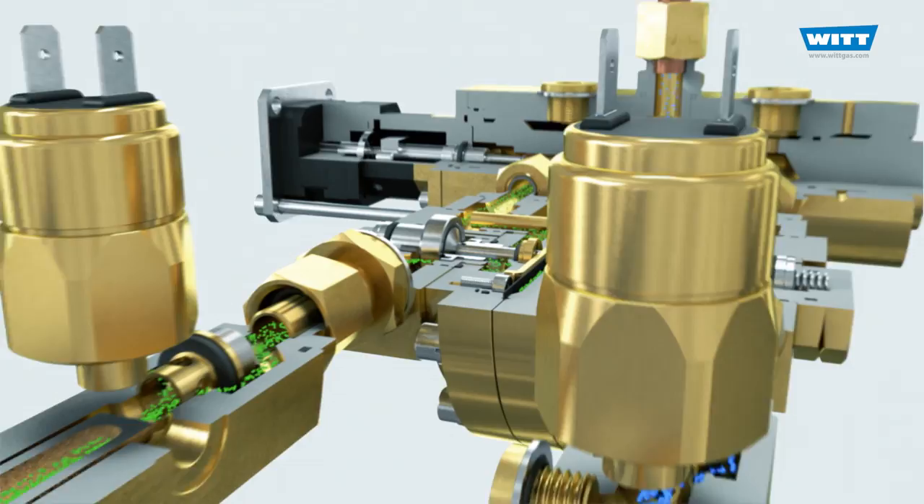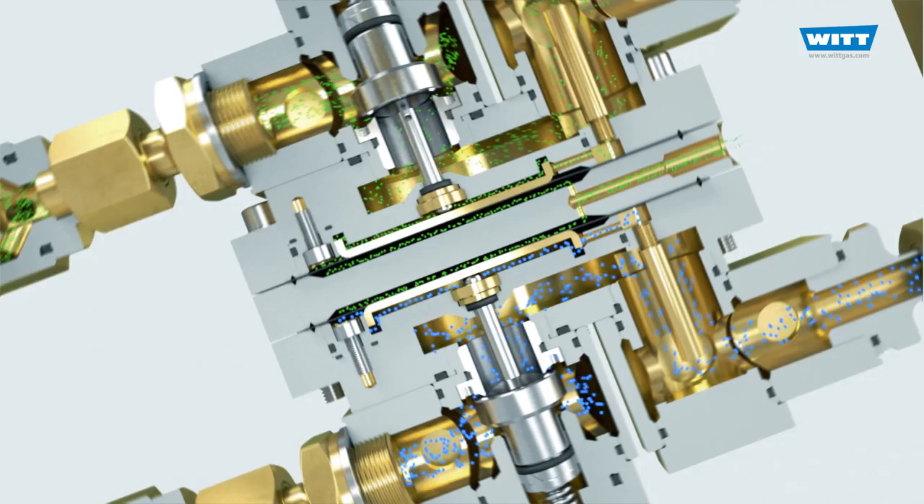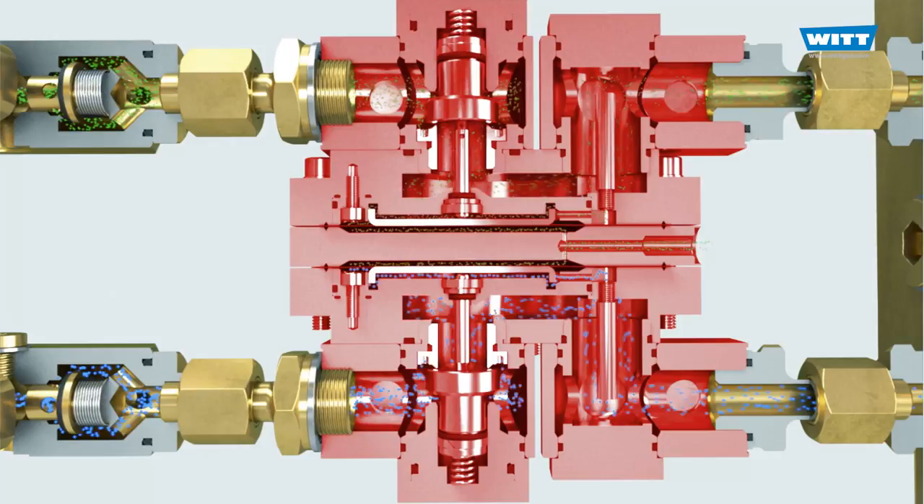Mixing valves require gases with equal inlet pressures to work correctly. Therefore, in the next step the gas inlet pressures are reduced and equalized by means of a pressure equalizing system. This is done by the proven WITT dome-loaded pressure regulators. Here we see a double dome regulator in a two-gas mixer.